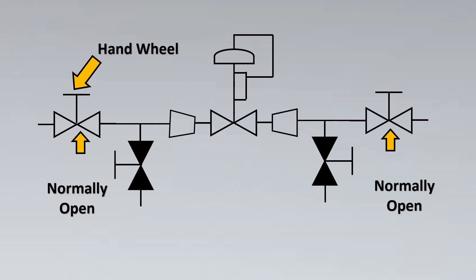Now usually in P&ID, if the valves are not colored it means that they are normally open, and the ones which are colored means normally closed. So sometimes in P&ID nothing is mentioned with respect to valves; just by the color we have to identify that these are normally open and these are normally closed valves.